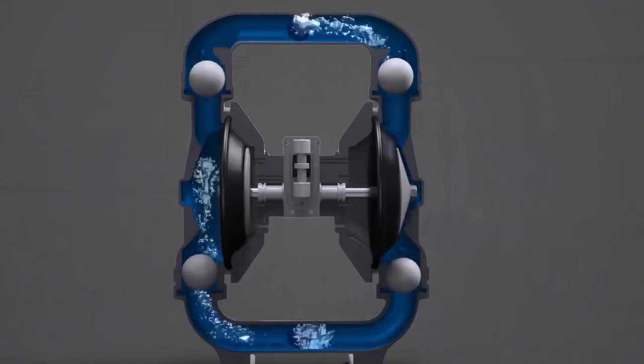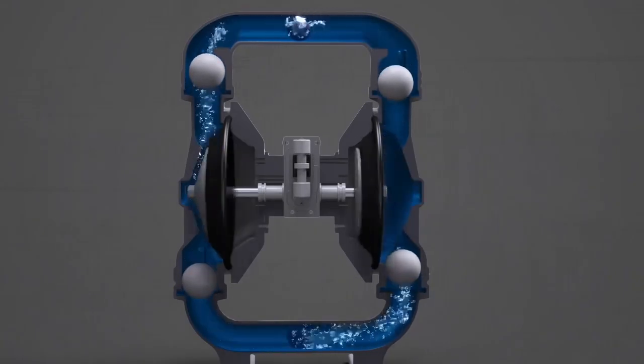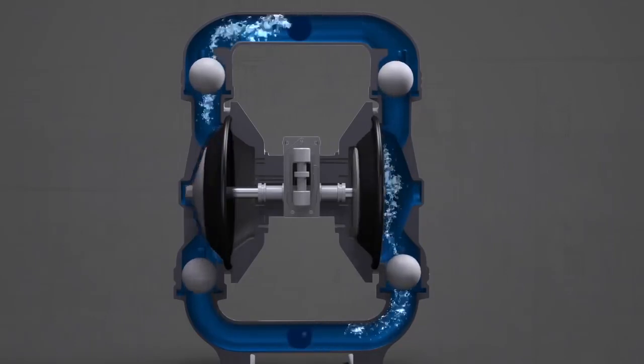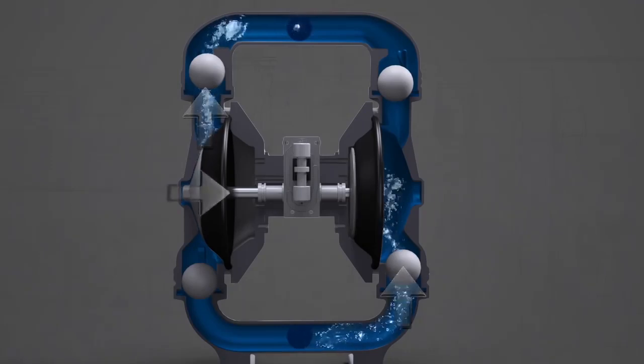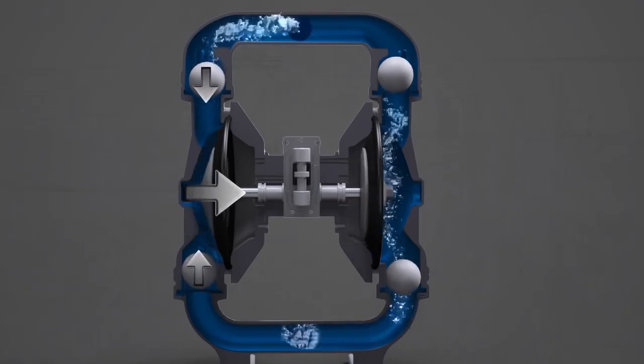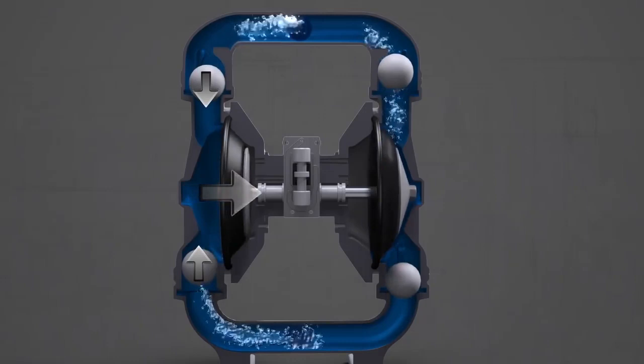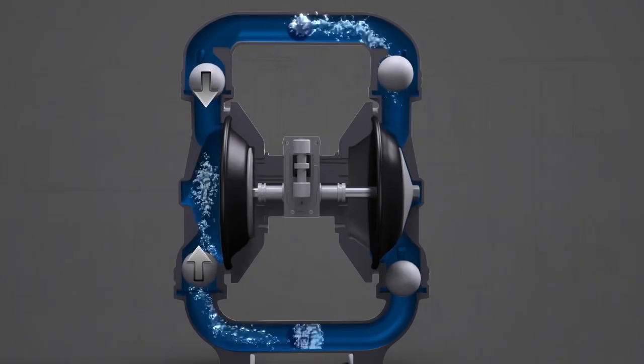Two diaphragms, connected by the diaphragm rod, work in unison to create the liquid motion of the pump. While one side is in suction mode, the other is in discharge mode. As a diaphragm moves inward, it creates suction. This suction motion causes the balls to move towards each other. As this happens, the top valve closes and the bottom valve opens. This allows liquid to enter the chamber through the bottom port.